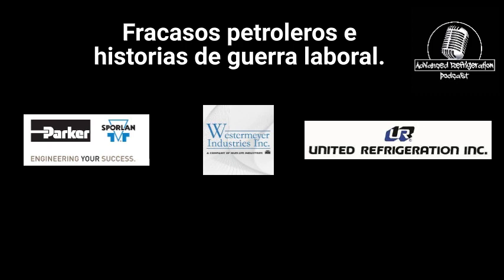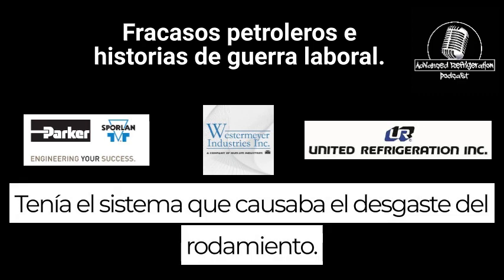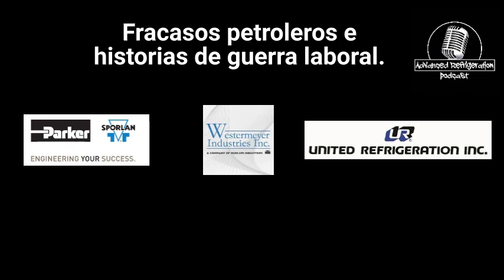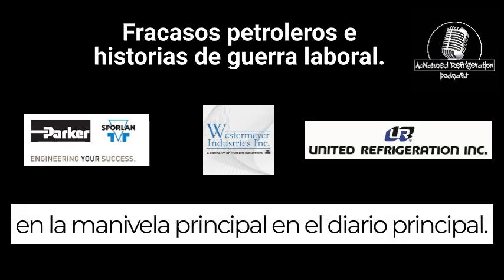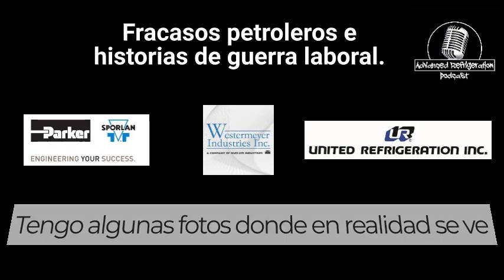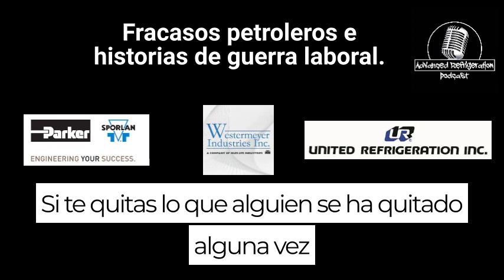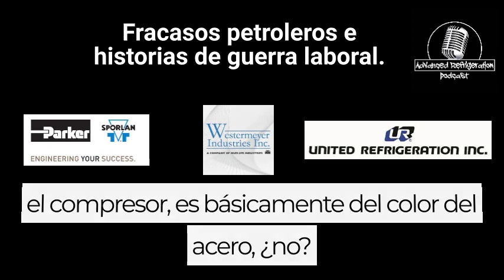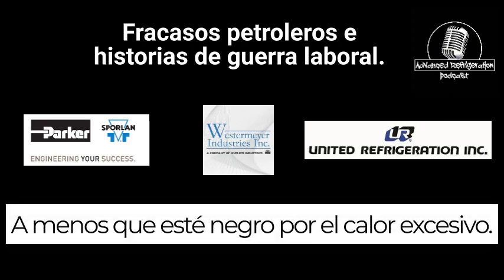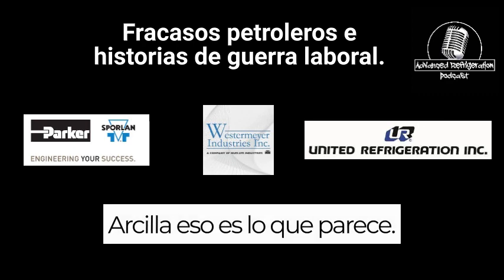Basically, in all my compressors, I had a problem in the system that caused bearing wear on the main crank, in the main journal. It basically caused the pistons to wear funny. I have some pictures where it actually looks egg shaped at the top. If anyone's ever taken off a compressor cover, it's the color of steel, right? Unless it's black from excessive heat. This looks like red clay. That's what it looks like.